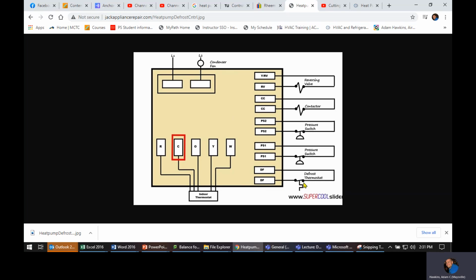If it needs defrost, this switch stays closed, then your orange switches, yellow stays energized because your compressor's staying on, your fan drops out, white gets power from red, sends power to the emergency heat, or the auxiliary heat, brings those on, the contactor stays energized, the reversing valve switches, and basically everything goes through its defrost circuit.